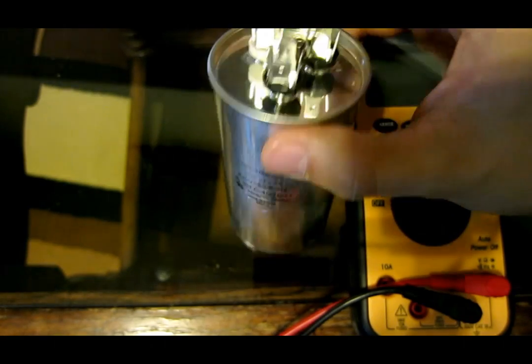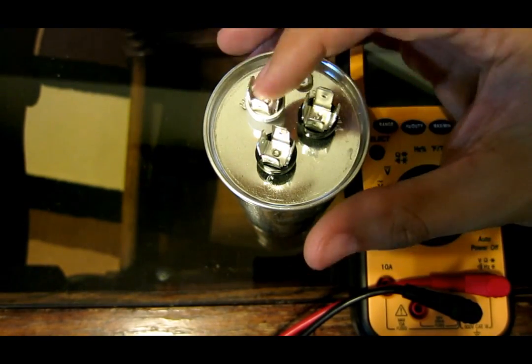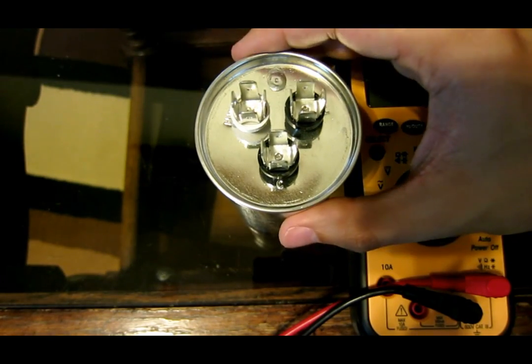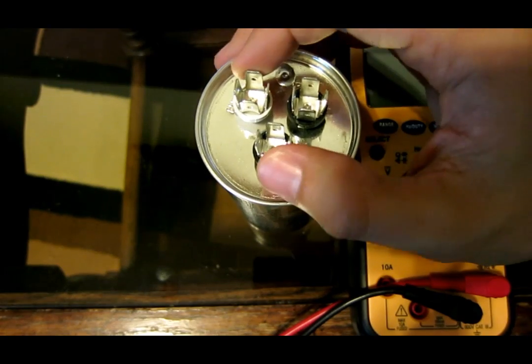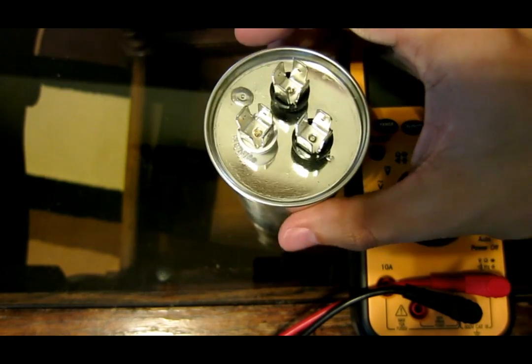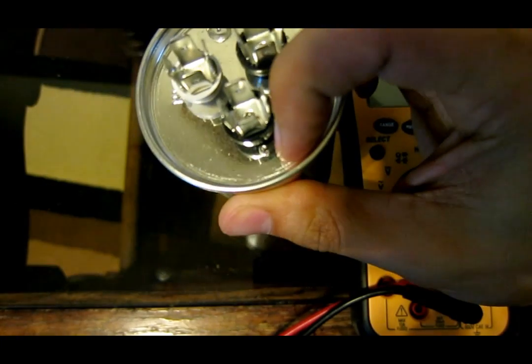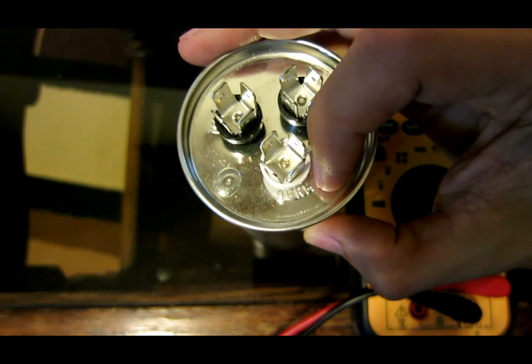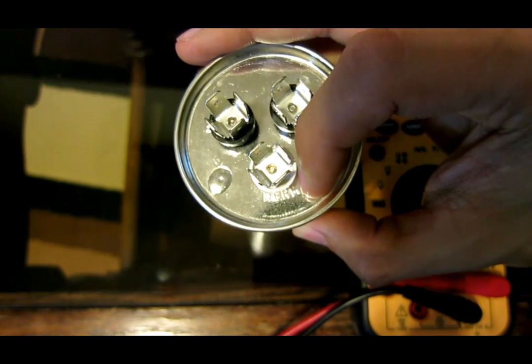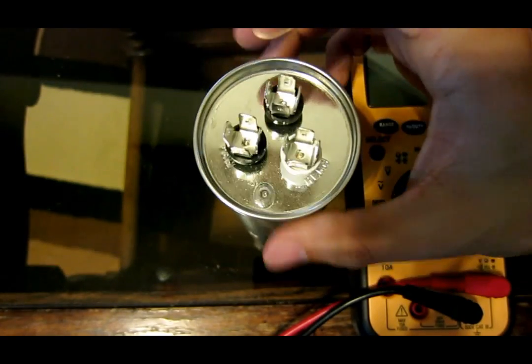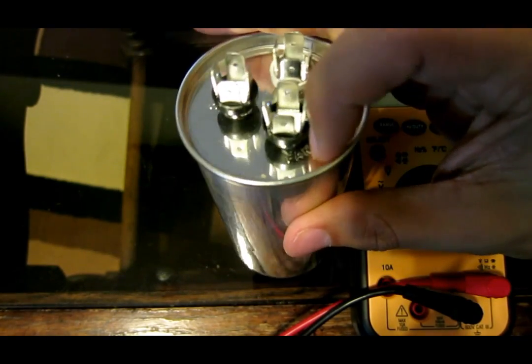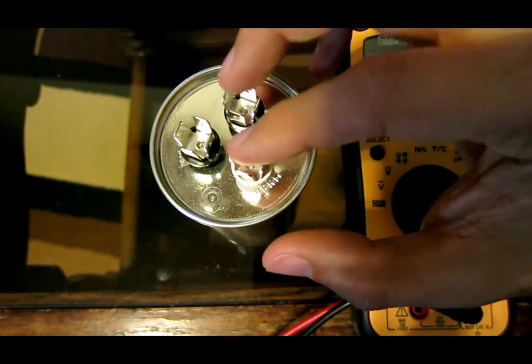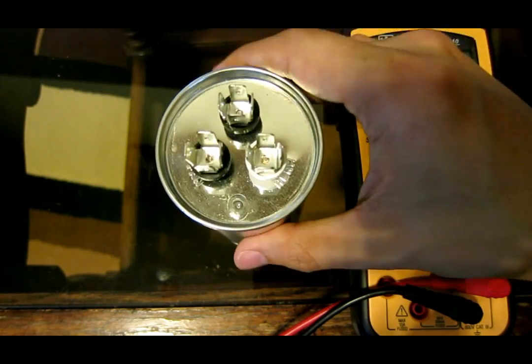Some run capacitors only have two terminals, and some have three. What happened is that they basically combined two capacitors into one. First of all, there are three things. First, you have your common, C right there. Then you have your HERM, H-E-R-M, this is where your compressor goes towards. HERM stands for hermetic, I think. And then you have FAN, F-A-N. Other capacitors might have common and FAN, and then you have another capacitor, common and HERM. But this one is all in one.